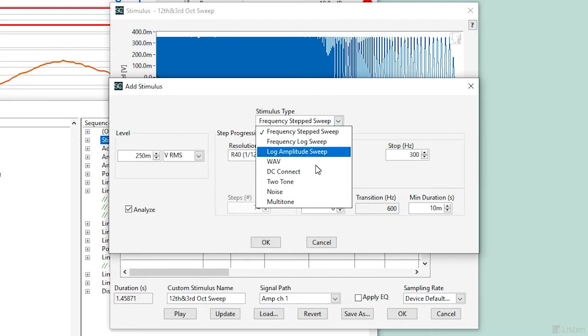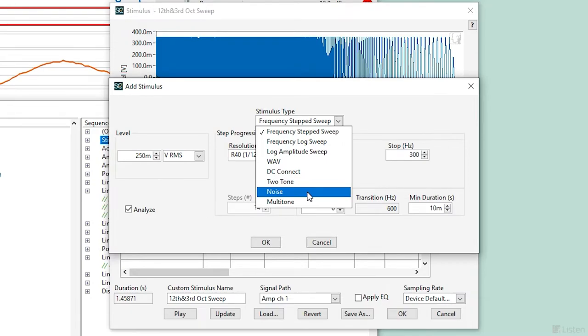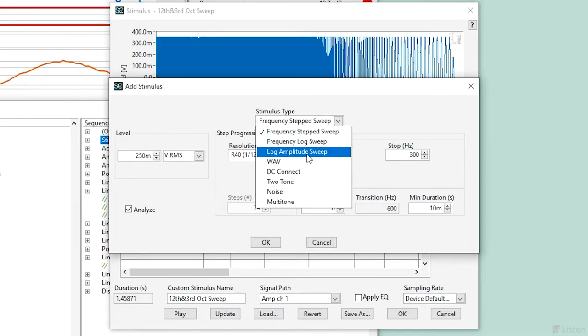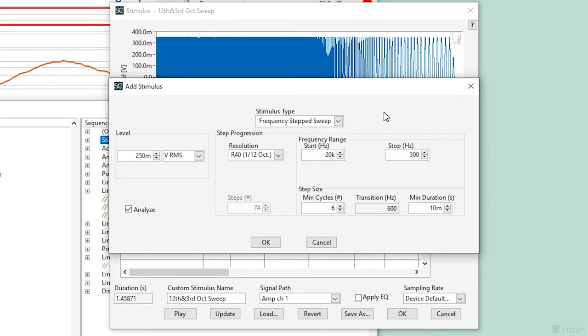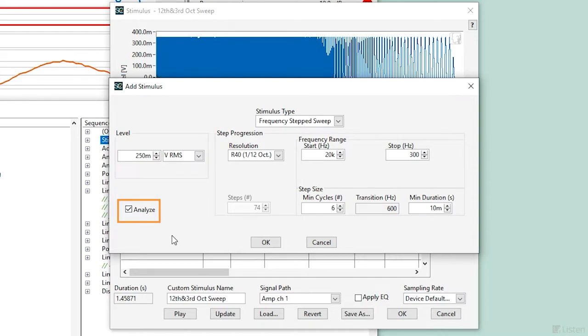There are other great uses of compound stimulus in SoundCheck. We can prepend noise before the test sweep and use it as a conditioning tone, effectively inject energy into the speaker to warm it before performing the measurement. We could put a tone or chirp at the beginning of the test signal when performing a trigger record in SoundCheck. Effectively, SoundCheck will trigger into record if the tone or chirp is identified and the input threshold is met. There's even an Analyze Check box so SoundCheck only analyzes the intended stimulus.